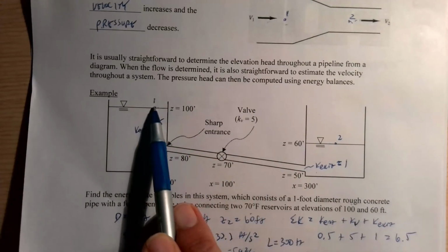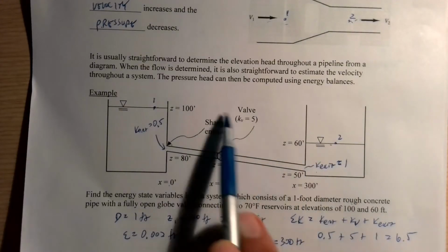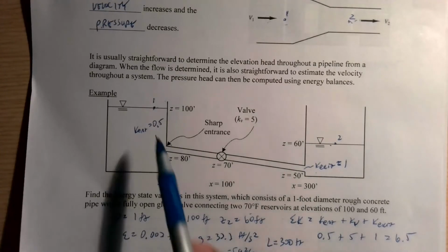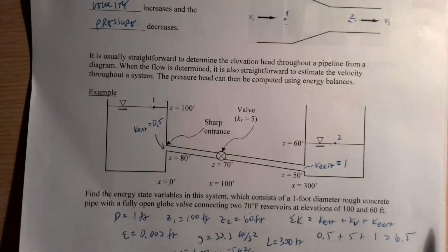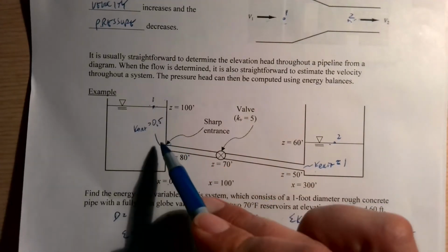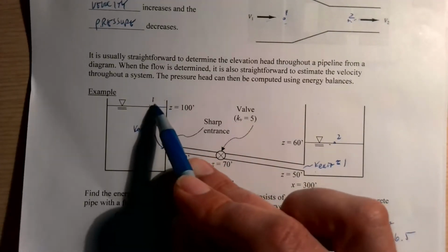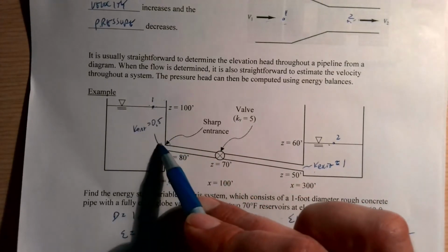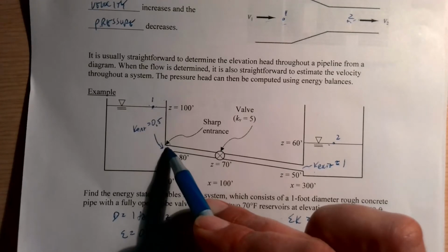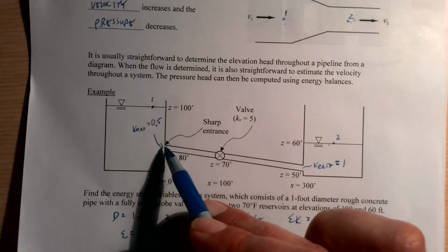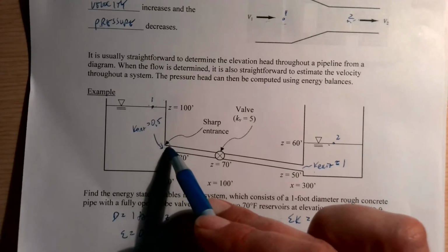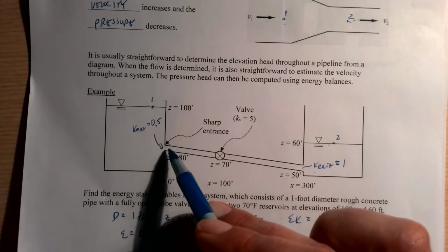As water goes from here to there, we are losing the 40 feet of head that separates the two, because we know the head at the beginning and the end. So we're losing some head. If we go down right before I get to the pipe, I'm trading all this elevation head for pressure head. So the elevation is going to drop, and the pressure is going to get bigger. Once I jump inside the pipe, I'm going to lose a bunch of energy from the entrance loss, so I'm going to lose a little bit more pressure head there. The pressure head's going to drop.